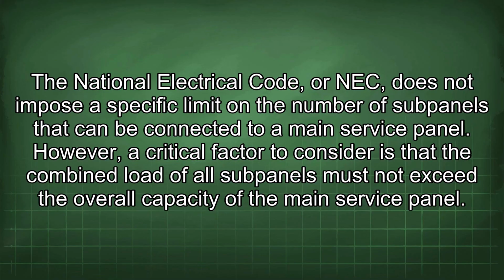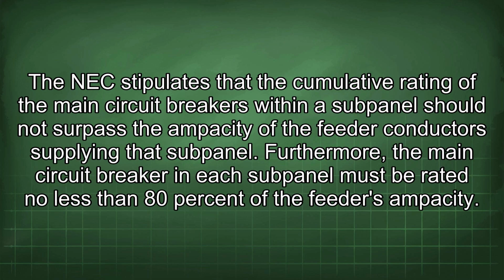The National Electrical Code, or NEC, does not impose a specific limit on the number of subpanels that can be connected to a main service panel. However, a critical factor to consider is that the combined load of all subpanels must not exceed the overall capacity of the main service panel. The NEC stipulates that the cumulative rating of the main circuit breakers within a subpanel should not surpass the ampacity of the feeder conductors supplying that subpanel. Furthermore, the main circuit breaker in each subpanel must be rated no less than 80% of the feeder's ampacity.